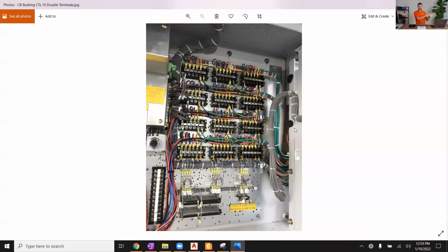That's the other end. That's the CT side that we're pulling from to bring into our relay current terminals. But sometimes you'll use transformer bushing CTs. I don't have pictures of that, but usually those transformer bushing CTs, you won't see them out on the bushings. They're usually buried down inside of the transformer tank. But if you were to go inside of the transformer control cabinet, you should see something somewhat similar to this idea of a whole bunch of transformer bushing CT current terminal blocks to work with.